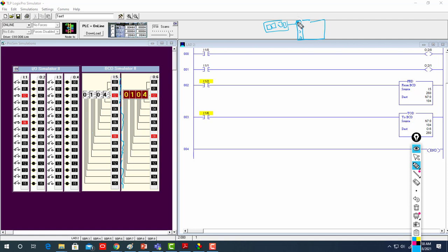So you have a special input module that you can buy. It reads the tumble wheel and converts it, depending on what you are giving. So to read the 104, you use the function FRD, because the tumble wheel module converts your decimal to BCD. That's what you need to understand. It converts your decimal to BCD.